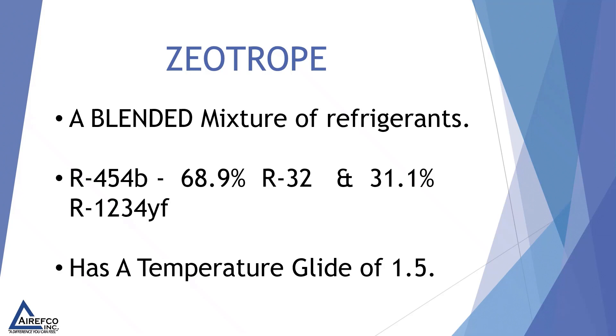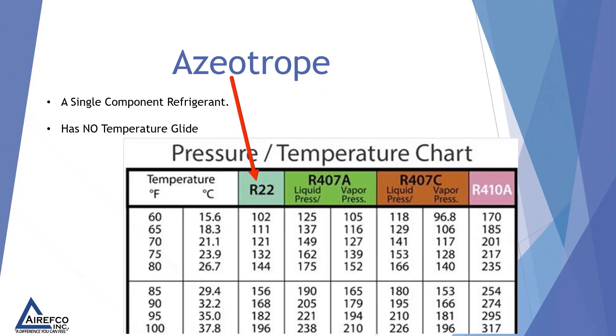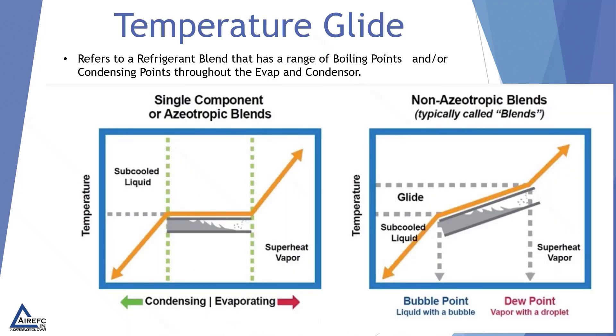Because R454B is a mixture, it needs to be handled as a mixture. R22 only has a single column on a pressure temperature chart, so it is an azeotrope refrigerant — a single component refrigerant with no temperature glide. R410A also has a single column but is technically a zeotrope; however, it has a very slight temperature glide, so we treat it as a near-azeotrope and it can be topped off like a single component refrigerant.